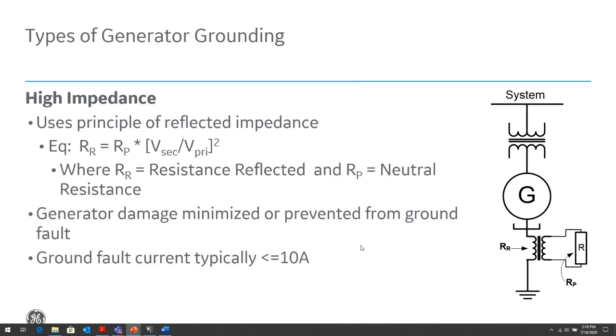Ground fault current in this case would be very low, as I mentioned. We're talking about less than 10 amps of primary current. Also, some of these installations will have a GSU, a generator step-up transformer, connected to the system through the generator. We do this to isolate ourselves from the system ground. Most GSUs are delta to Y transformers. If the delta is on the generator side, it allows the generator to be isolated, ungrounded, while on the system side it's a Y grounded winding, so it allows the system to have its ground, so that if there's a ground fault, the system can detect it and take corrective action. At the same time, if there's a ground fault on the generator, we don't see any ground current in the generator.